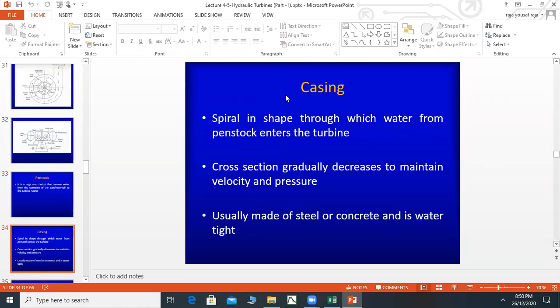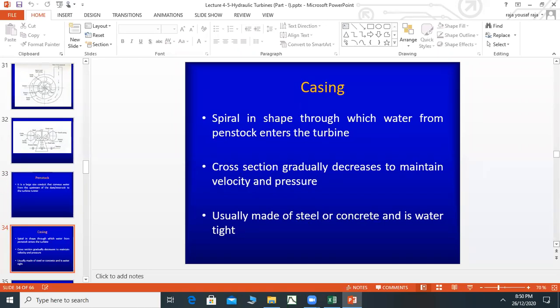The casing is the outer body of the turbine, spiral in shape, through which water from penstock enters the turbine. The cross-section gradually decreases to maintain velocity and pressure. It is usually made of steel or concrete and is water-tight, so that water does not leak from the turbine.